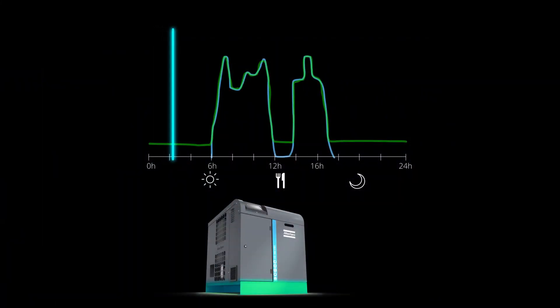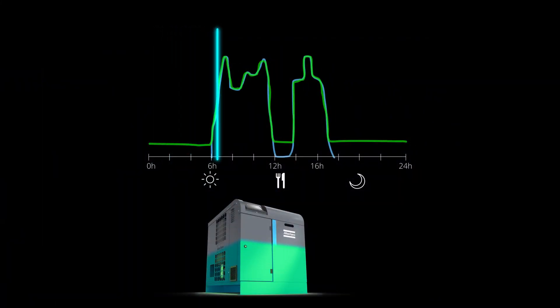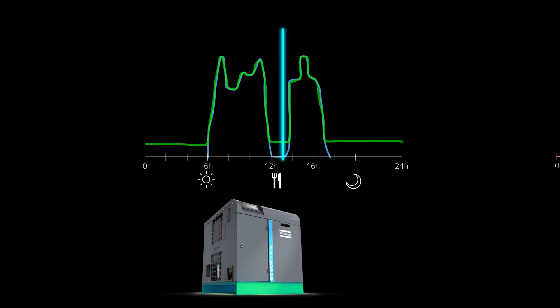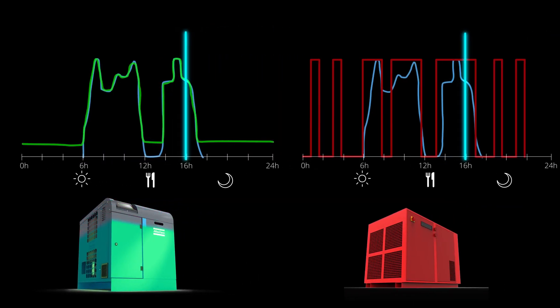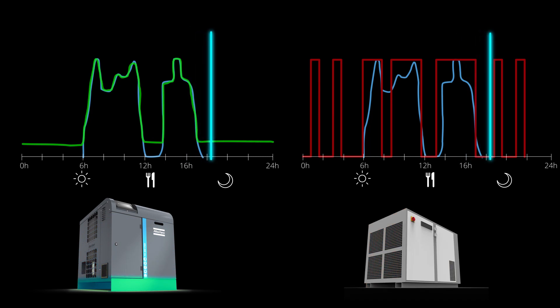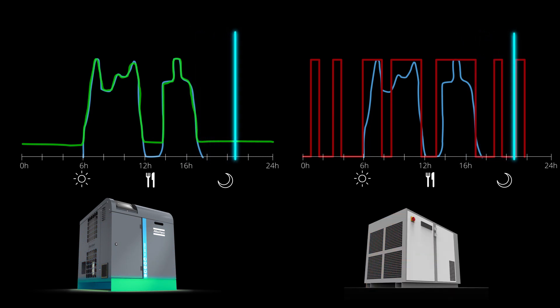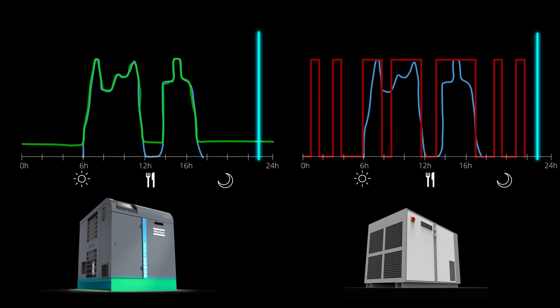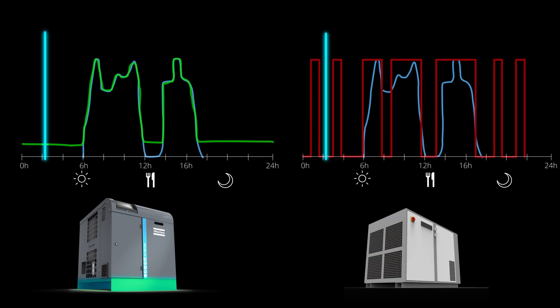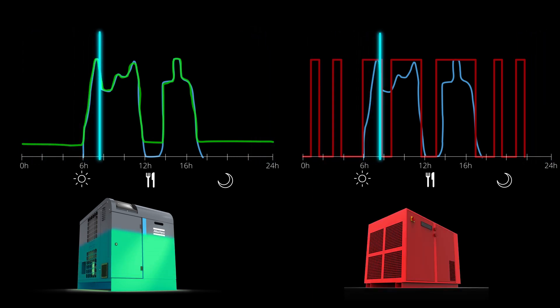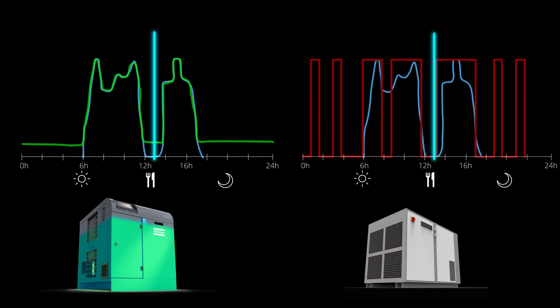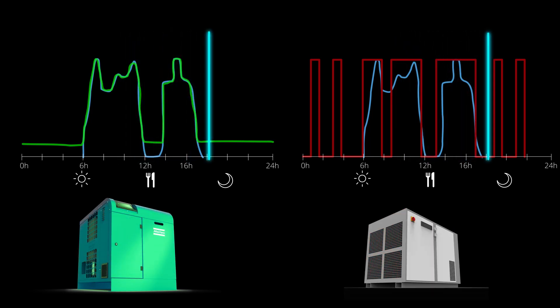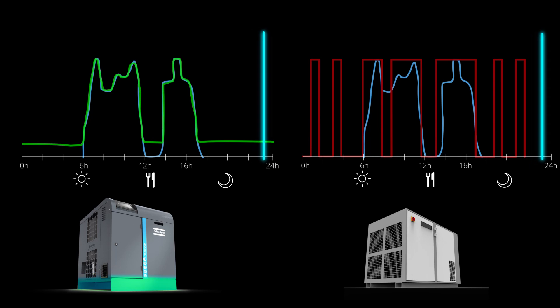First, the FDVSD offers much higher energy savings as it follows your actual need for compressed air. The thermal mass dryer simply cycles between running at full load and relying on thermal mass for cooling. The FDVSD already saves energy where cycling dryers still have to spend energy to cool down their thermal mass.